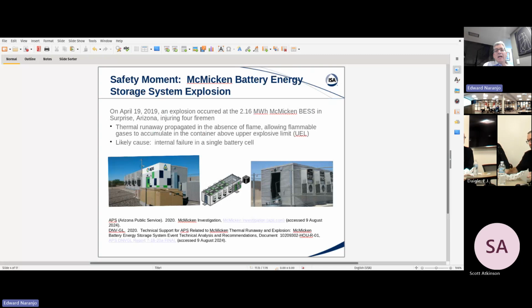Once these failures occur, because of the heat emitted by these batteries, they can start propagating and burning other cells, releasing additional hydrocarbon gases and even toxic gases, creating a cascading effect. In this case it didn't go that far, but the explosion was sufficient to injure personnel. Luckily no one was killed, but it's a reminder of what can happen in one of these units.